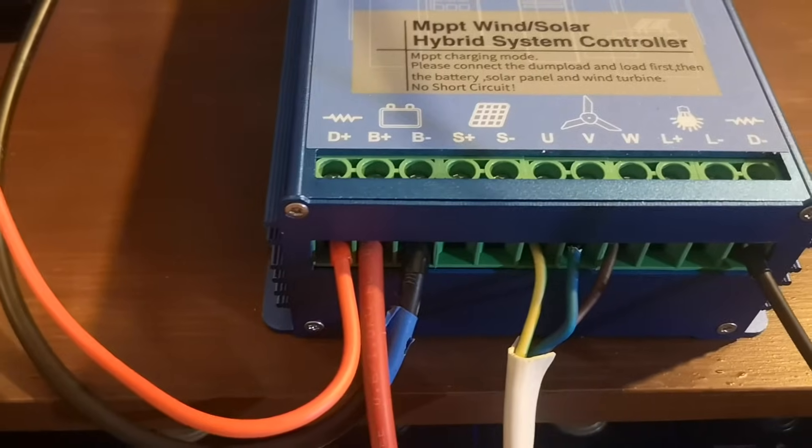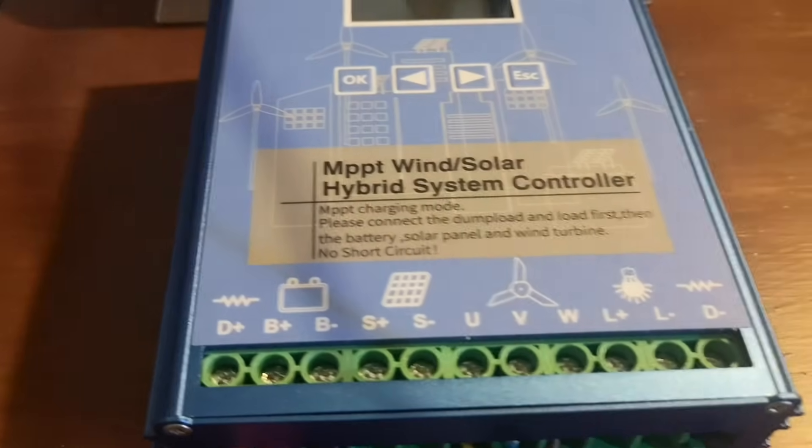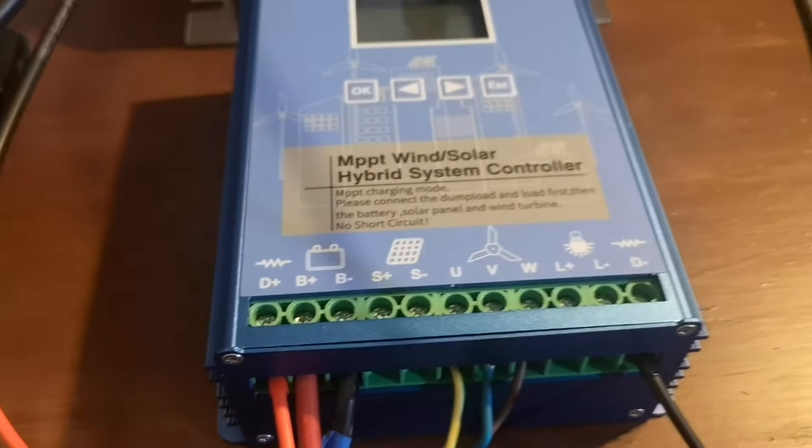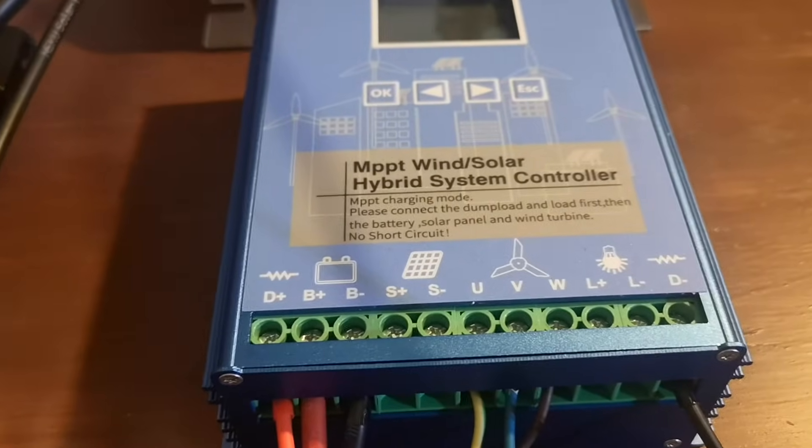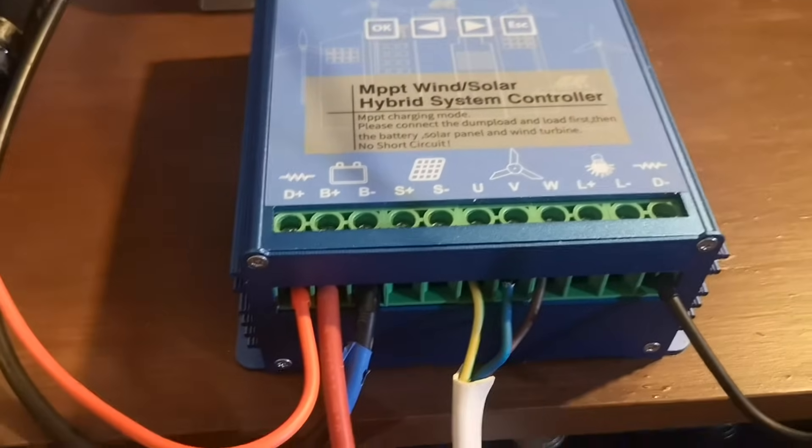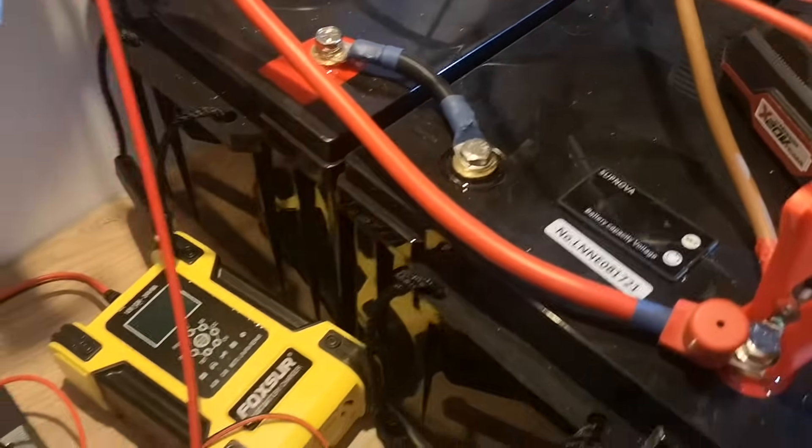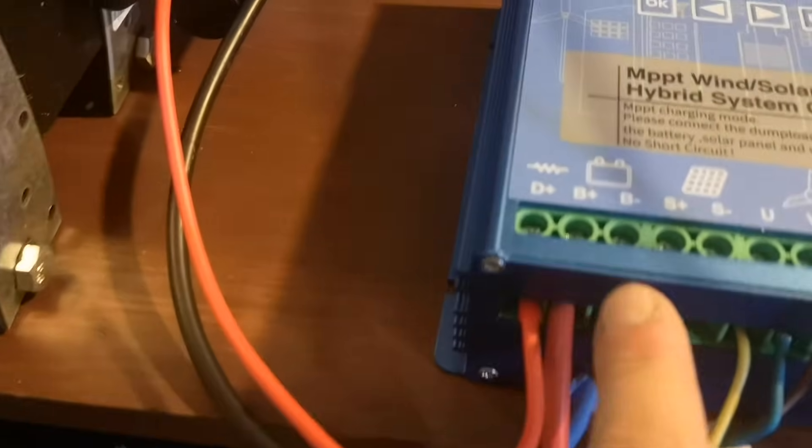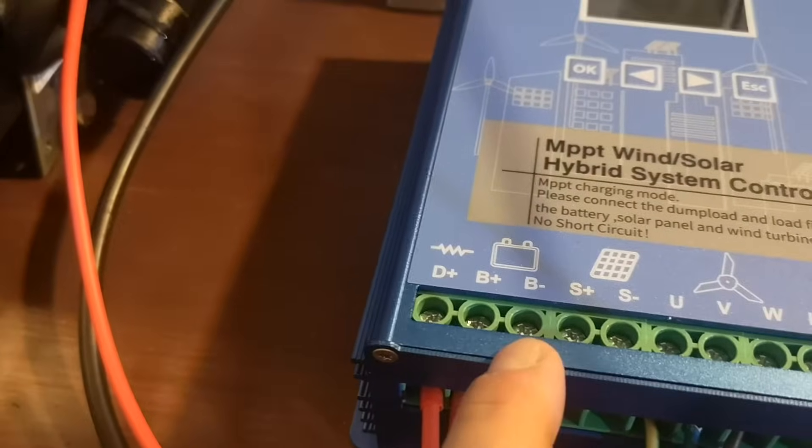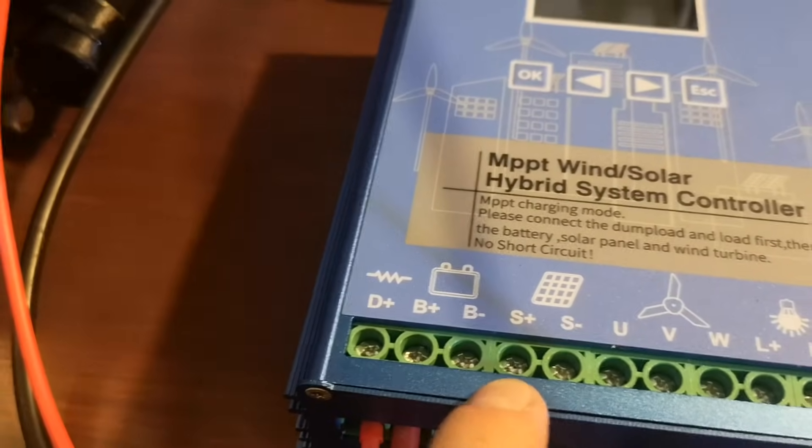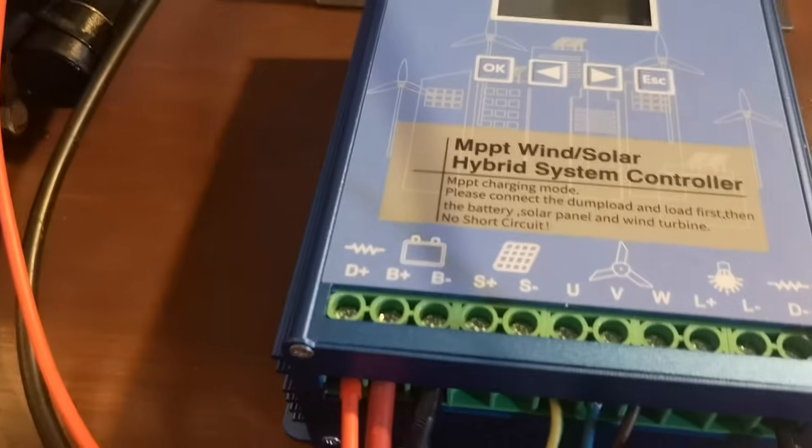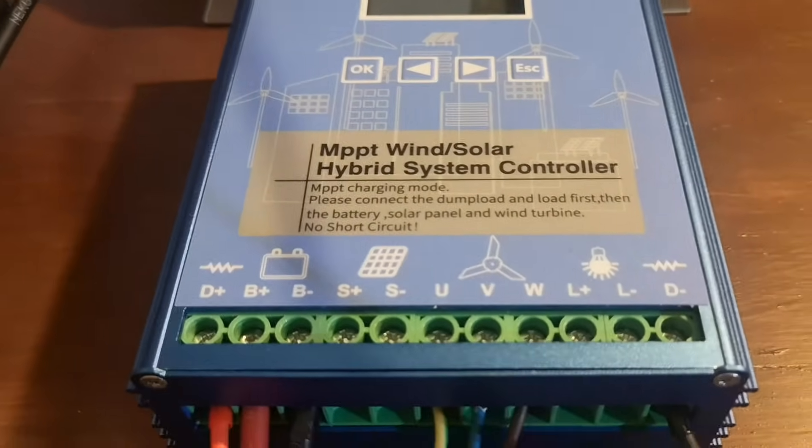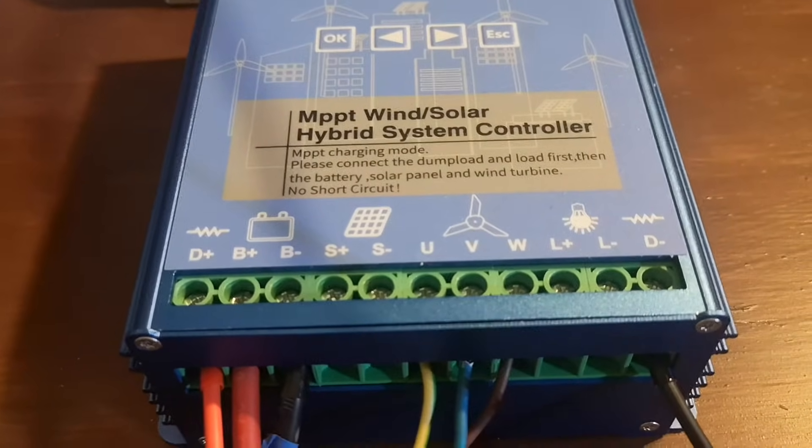At the next step you're connecting battery. This particular version is 12 or 24 volts, but there are also versions 24 and 48, so make sure this is compatible with the voltage of your battery. In my case I will be connecting it into my lithium iron phosphate batteries 24 volt system connected in series. So we're connecting plus and minus into battery positive and negative. If you have a solar panel you're connecting it here into solar plus, solar minus. The maximum voltage on this particular 600 watt model is only 50 volts, so pay attention not to over those with the voltage.